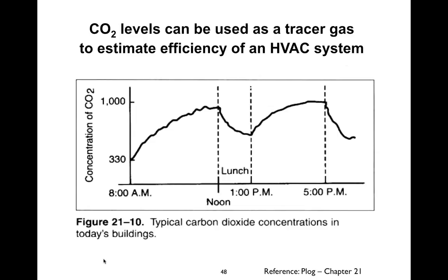So, does it look like this particular facility is exceeding the ASHRAE standard for ventilation with outside air? Quick guess, quick answer. Somebody give me a yes or no. Are we exceeding the ASHRAE standard here? Okay, I got one yes. Any other yeses? I'd say it's borderline because it looks like they're peaking out at just about 1,000, right?